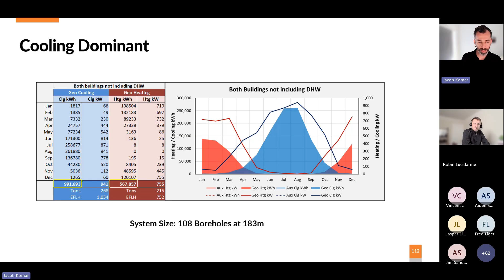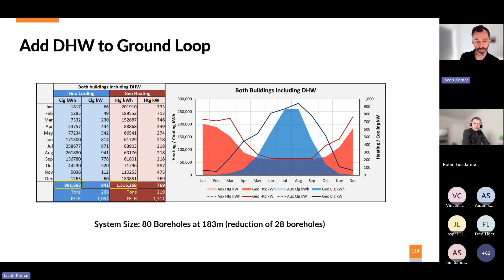We needed 108 boreholes, and the ground temperature was rising over time. So we added hot water demands to balance out the loads. We reduced our borehole count to 80 boreholes, and now it's a lot flatter.